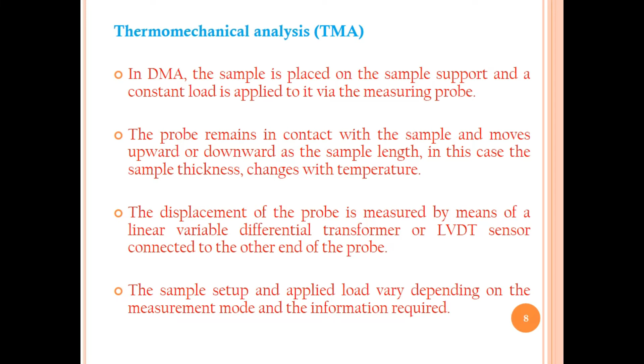Now we will describe a bit about the TMA. Here is a block diagram of TMA. This is the same type of diagram that we already discussed in DMA, dynamic mechanical analysis. Here is a force generator to apply force to the sample, an LVDT detector, and a probe that is in contact with the sample. A thermocouple serves as the temperature sensor measuring the temperature. The sample is placed at the bottom of the furnace, which is used for the temperature provision to the sample under investigation. That is the sample cylinder in which the sample is placed. The sample is inserted into the furnace and is touched by the probe, which is connected with the length detector and force generator, as clearly shown in the block diagram of TMA.